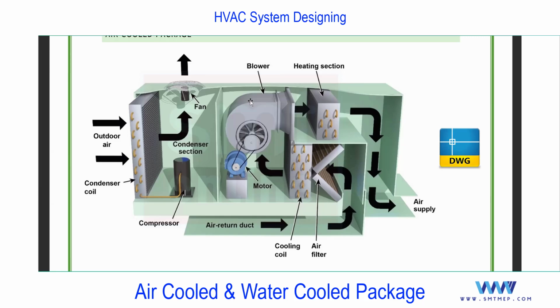Means I'm talking about the size of the system. You can expect the higher efficiency even in air cooled, but the size of that air cooled condenser will increase. So if you want higher efficiency with compact size, you can expect it in water cooled system. This is the main point. Apart from this, we have some more points to discuss.